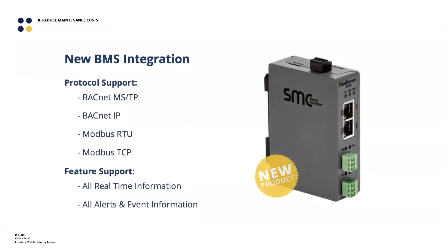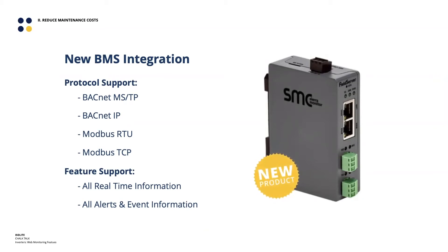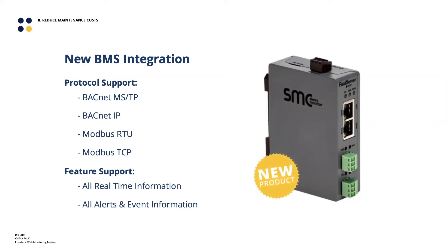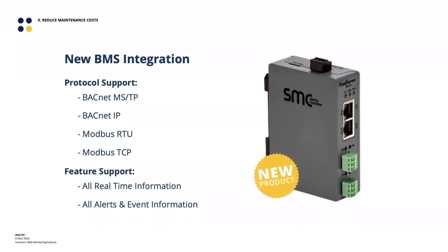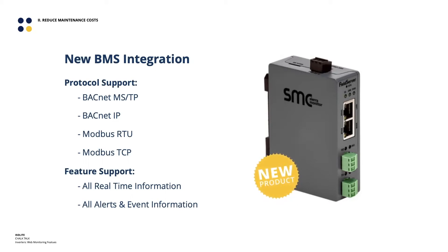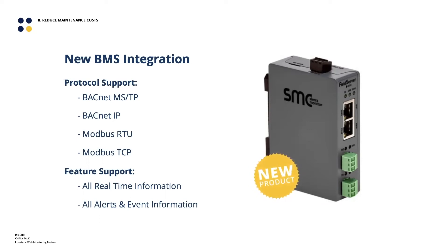We've been asked for a more standards-compliant solution allowing facilities to utilize an existing BMS system, and I'm excited to announce today that we've done that. We've partnered with Sierra Monitor and their FieldServer product — Sierra Monitor has implemented custom firmware so it knows how to talk to an inverter. Through this FieldServer device we get compliance with multiple protocols: BACnet MSTP, BACnet IP, Modbus RTU, and Modbus TCP. It's pretty flexible.